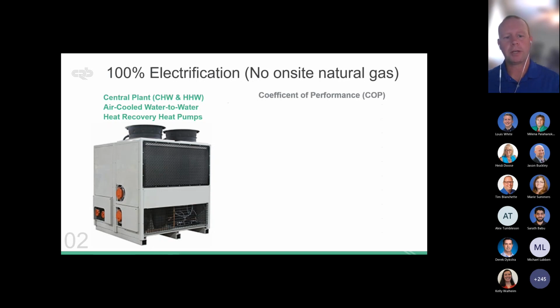A lot of people will say, well, natural gas is so cheap, so why wouldn't I want to use natural gas? And I'll say, well, it is cheap - maybe on the magnitude of 3 to 4 times cheaper than electricity - but it's also not that efficient. A natural gas boiler might be 90% efficient, so it's got a COP of 0.9, output over input. When you go electric resistance, you get 100% efficient - all of that electricity goes into a wire that heats the medium. So it's 100% efficient, you can't do better than that, which is true for thermal conversion, but untrue when you're talking about thermal movement.